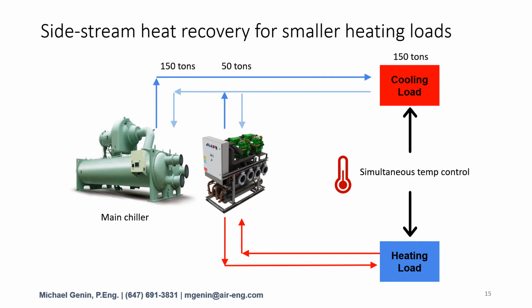This heat recovery chiller is dedicated to serving the hot water load. The cooling load is much larger than this chiller could ever supply, so the remainder of the chilled water load is made up by the main chiller. This results in simultaneous temperature control of both the hot water and the chilled water.